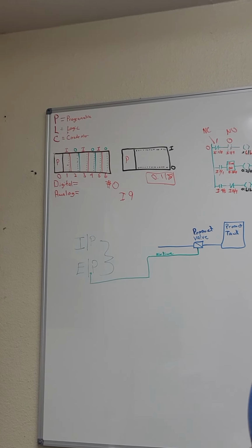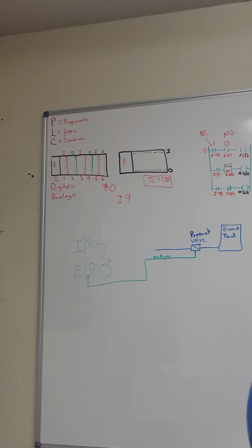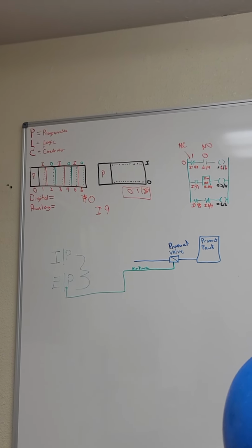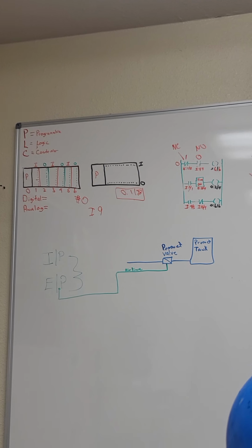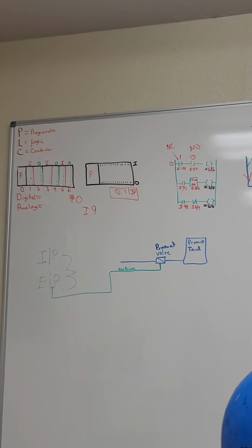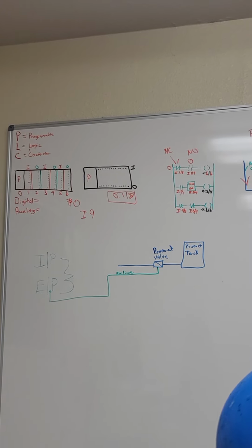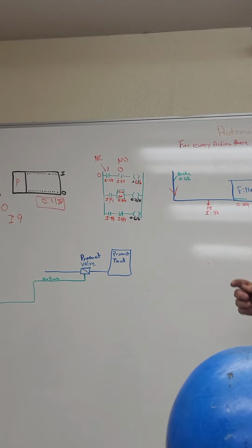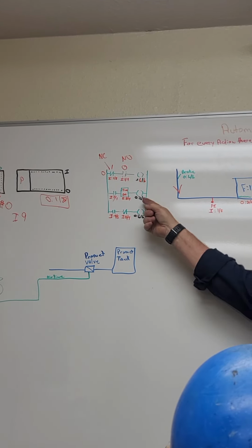So every time a bottle goes by, we're gonna shut off the infeed? No. It has to be blocked for a certain amount of time. Remember when we did that photo eye down there on number 5, and I sped it up, because it was jerking that night every time a ball went through. That's why you put a timer in here. It has to be blocked for 3 seconds before it fires that output.